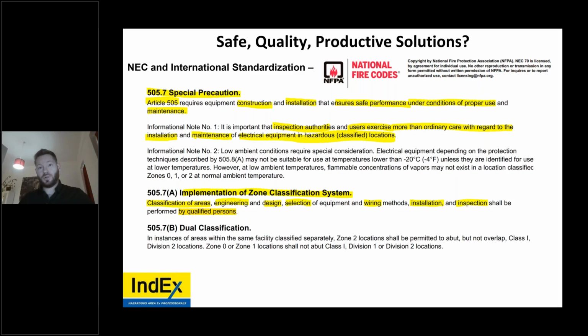Perhaps you should include a chemical, process, mechanical, electrical, and instrument engineer, like they do for HAZOP, HAZID, when defining their safety integrity level requirements, their SIF, their SIL, for their facilities. Does functional safety go before hazardous area considerations? If a gas detector detects gas, but was not selected to be hazardous location protected, with an Ex protection technique, it can detect gas, but could also ignite it. It doesn't sound like a good idea. Probably best to order, let's say, an Ex d flameproof gas detector, then figure out which SIL rating. That would seem to be the common sense approach.